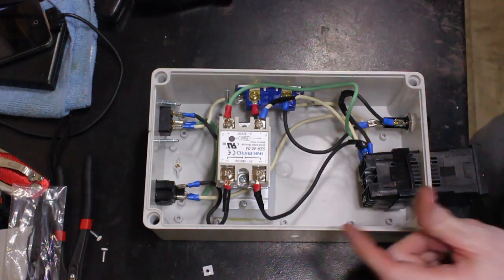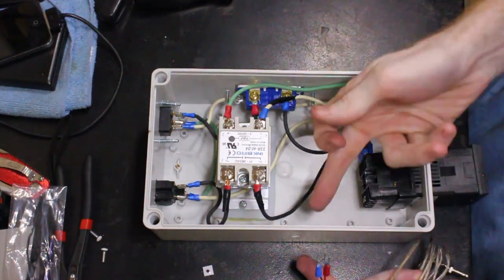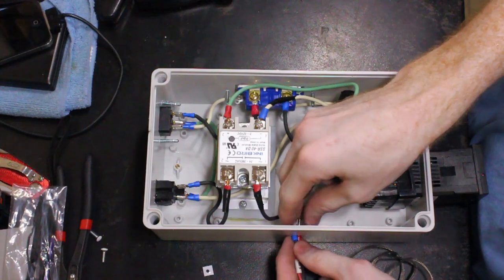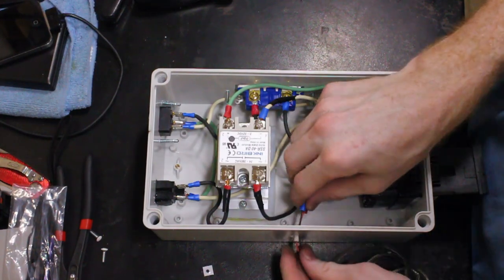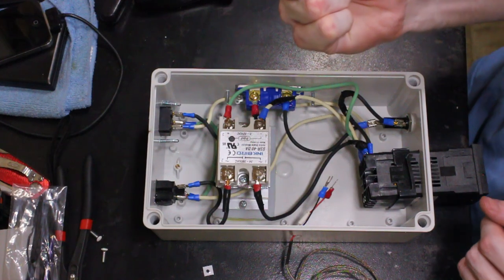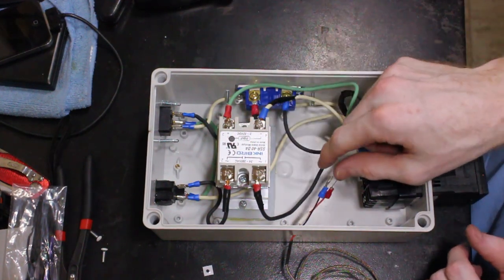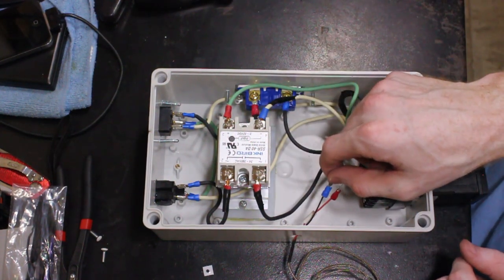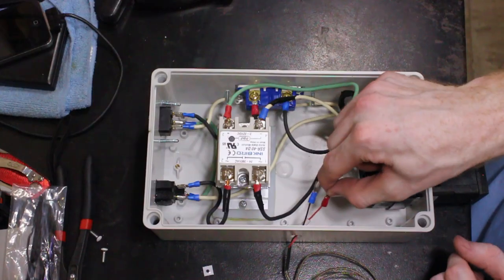All right, so that is the full wiring. The last thing to do is to connect our thermocouple. So our thermocouple wires will come through this hole right here. I'm going to be connecting the blue wire on top and the red on bottom. You'll know if you have them mixed up due to the fact that when you hold the thermocouple, you won't get hotter, you'll get colder. So we're going to hook up the blue one to our number nine, which is negative, and our red one to number ten.